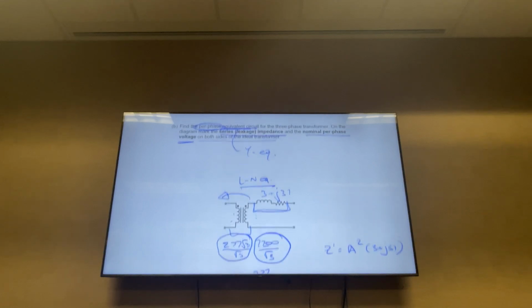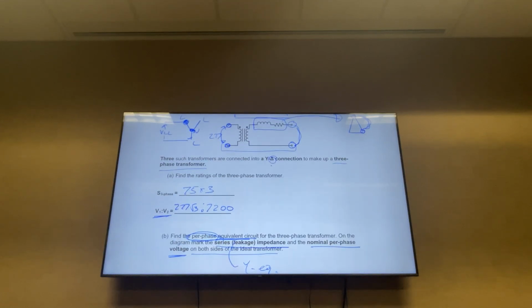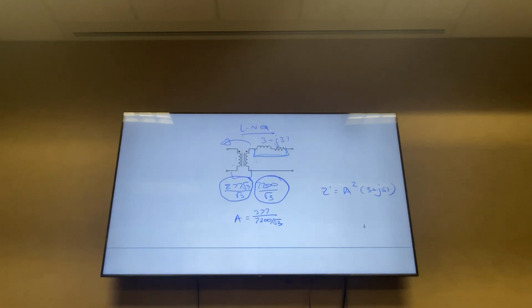Let's write that out. Multiply by a squared. So Z prime will be a squared times 3 plus j31, and a would be this ratio of 277 divided by 7200 over square root of 3. Which is the same ratio as 277 times square root of 3 over 7200, right? Yeah, the same. Okay.